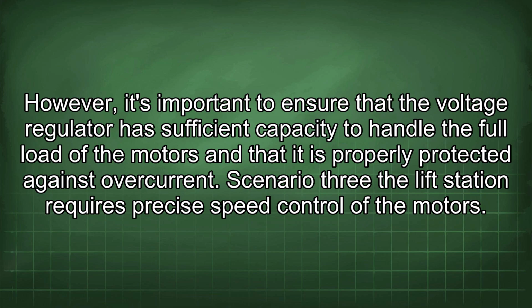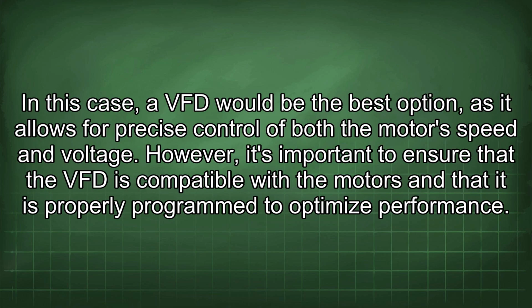Scenario 3: the lift station requires precise speed control of the motors. In this case, a VFD would be the best option, as it allows for precise control of both the motor speed and voltage. However, it's important to ensure that the VFD is compatible with the motors and that it is properly programmed to optimize performance.